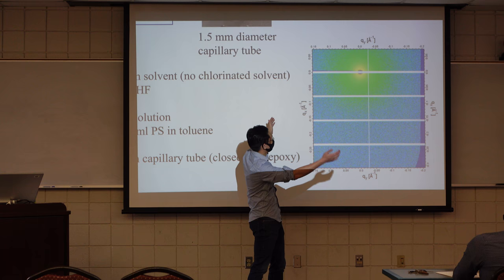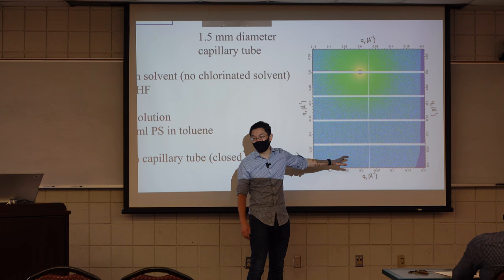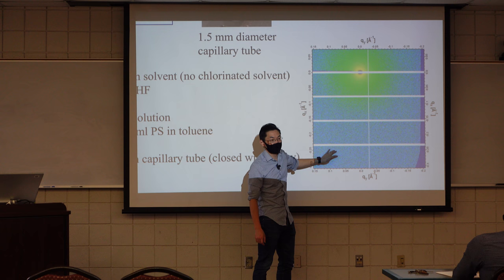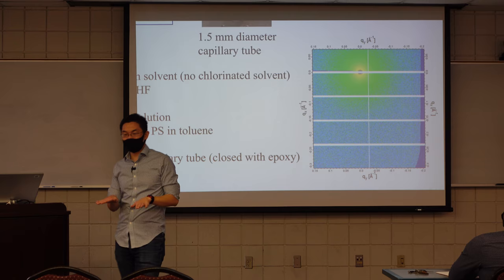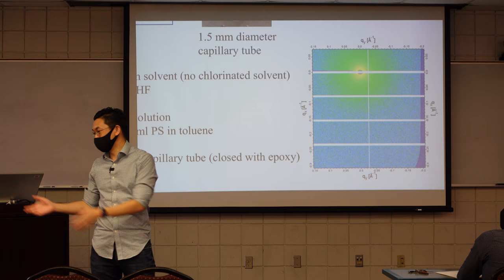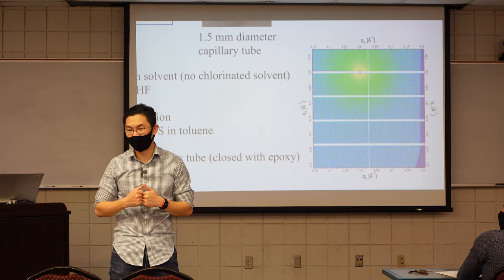You make a large detector, right? Because you cannot throw it away. So what people make then is by making small modules. So this one particular strip, yeah, this 1/10 of this square is one mini module. This was made by them. Then they basically assemble a large detector by putting 2x5 arrays of them. Okay, so if you have one particular area that is pretty bad, then you just need to throw away 1/10 of the area. You can still use it, it improves the yield of their detector.